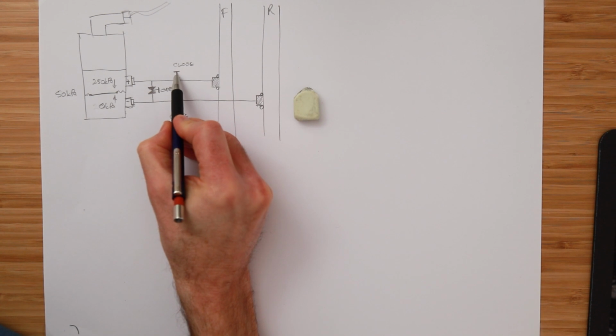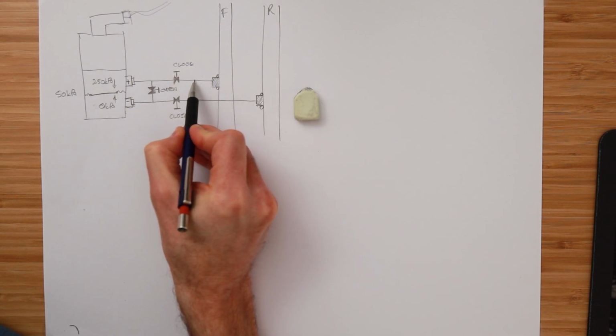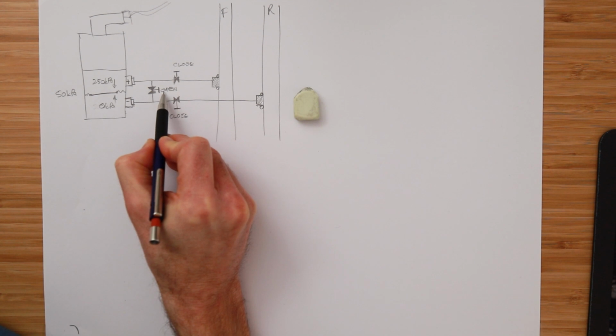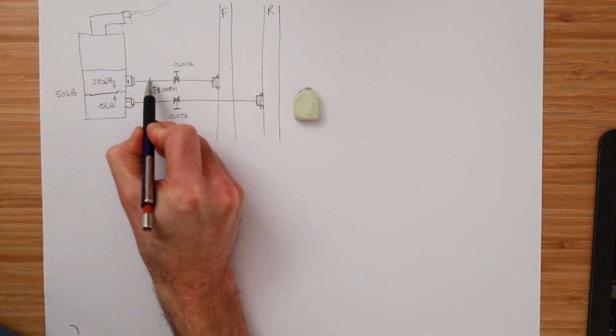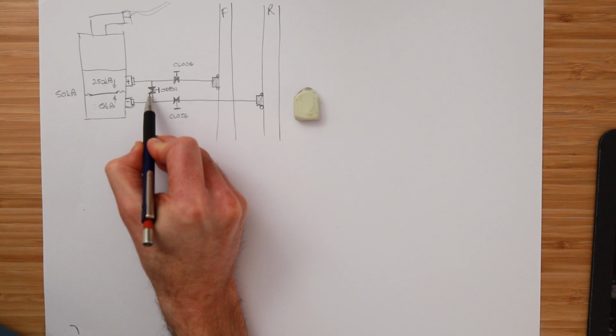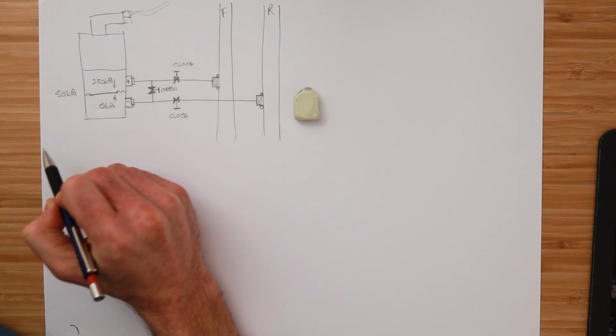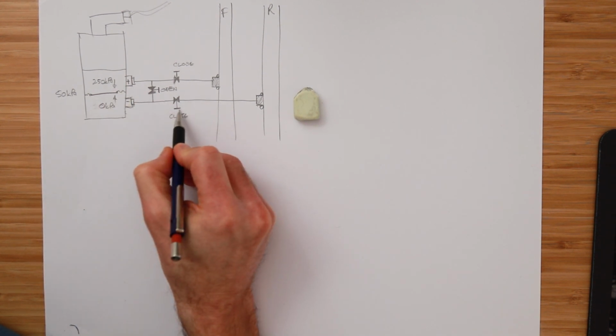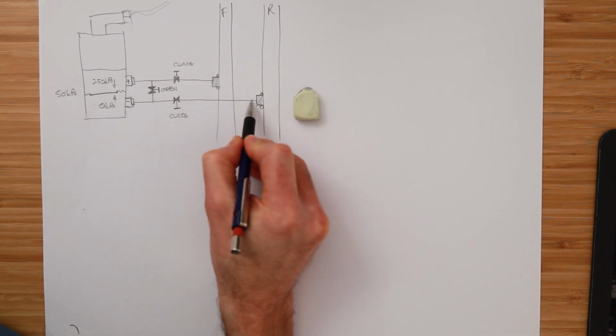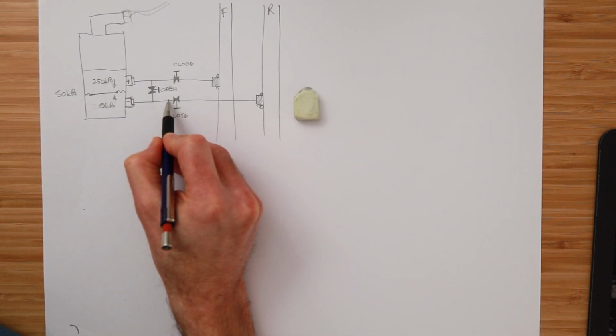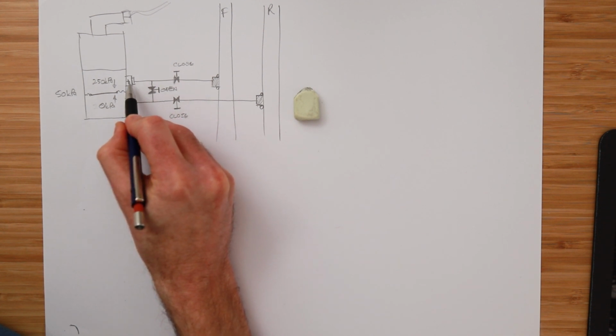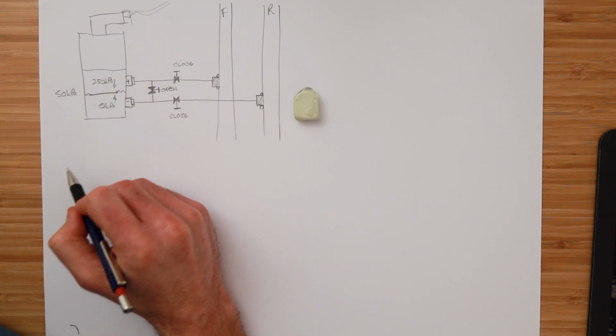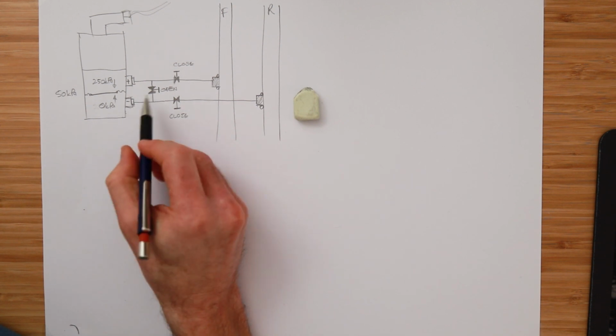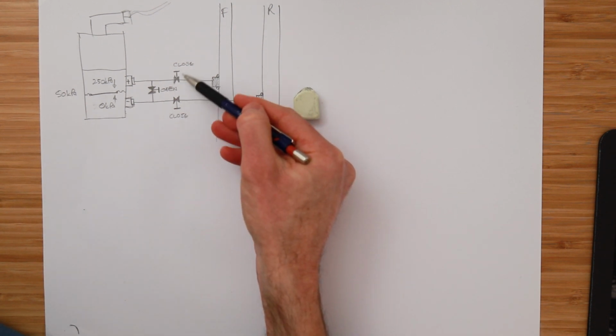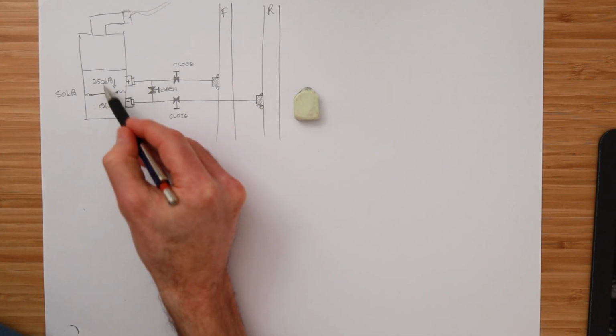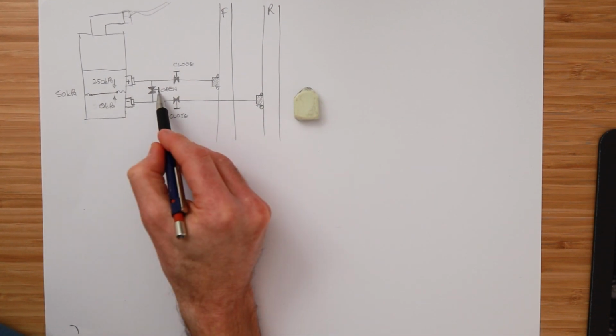And then when they open this one through the leak test, the pressure comes through here. Because this is open, it comes through both of them, and it applies this pressure equally to both ports. The diaphragm does not burst. Then he opens this one to check for leaks in this pipe and this connection over here. The pressure comes through, stabilizes through the bypass. The pressure is the same. Then you close this. So the sequence is open this first, open these 2 however you want in any sequence. Once the pressure across the diaphragm is balanced, then you close this again.